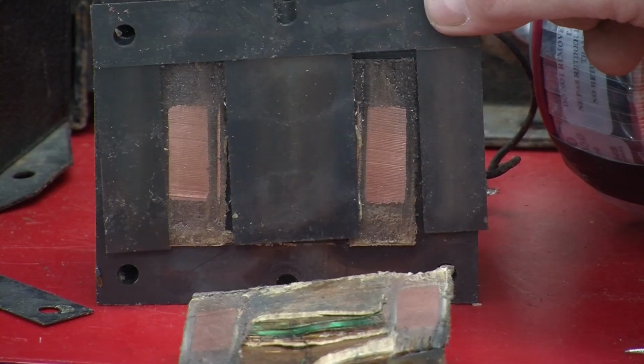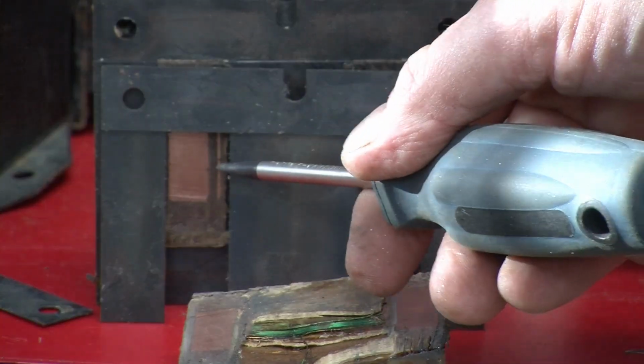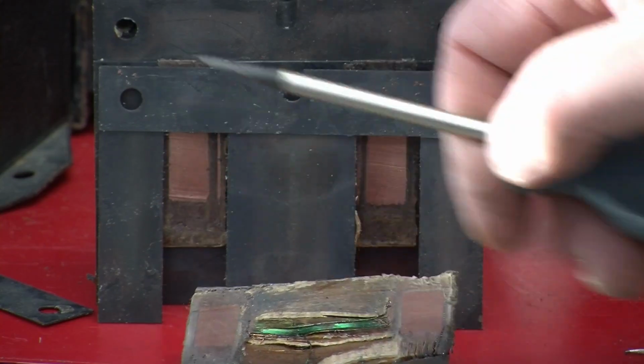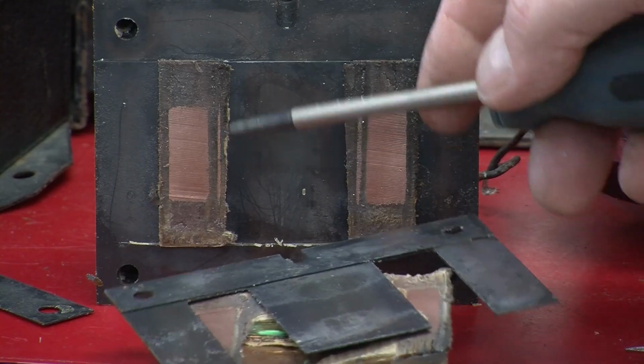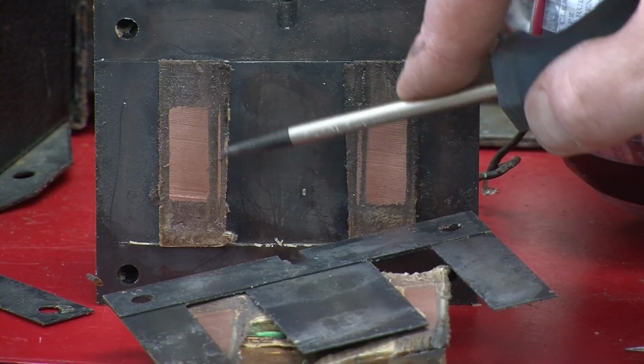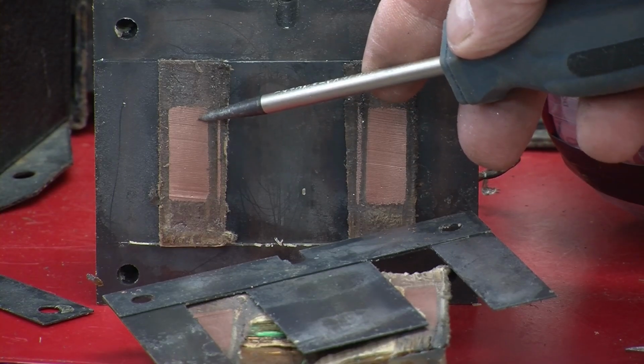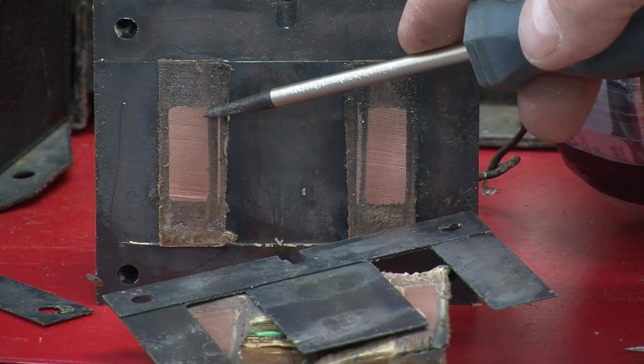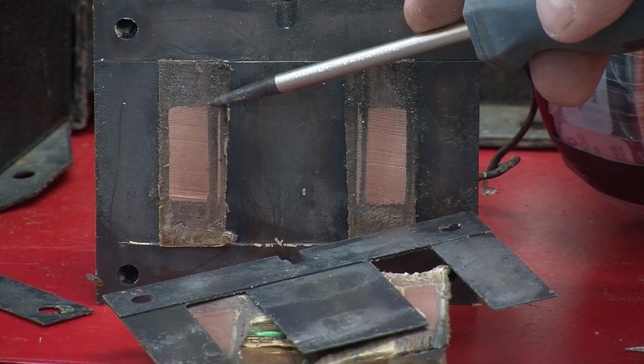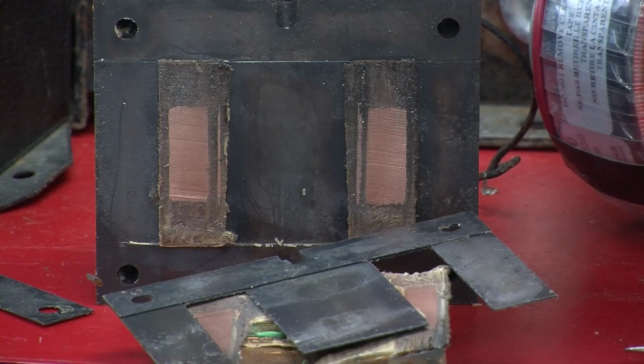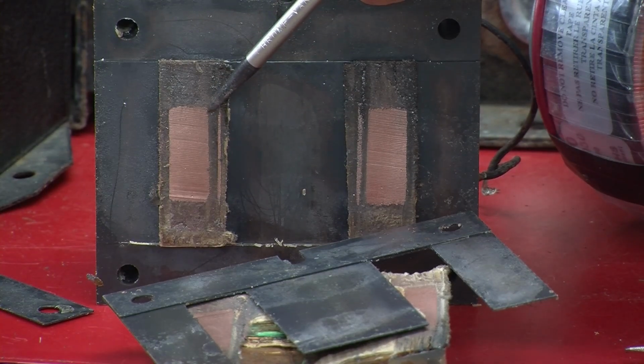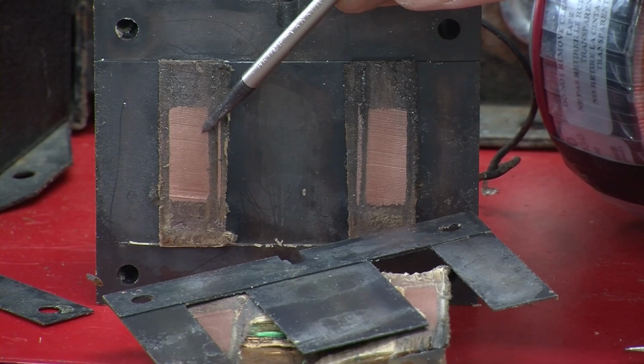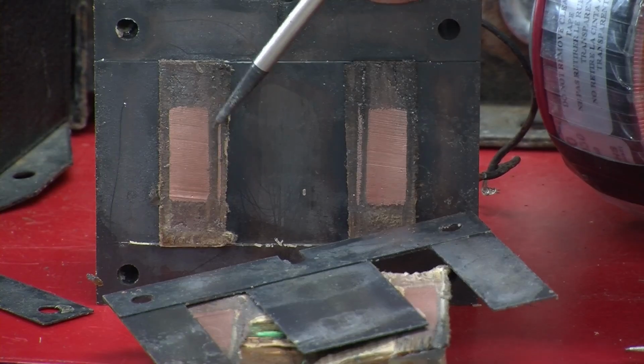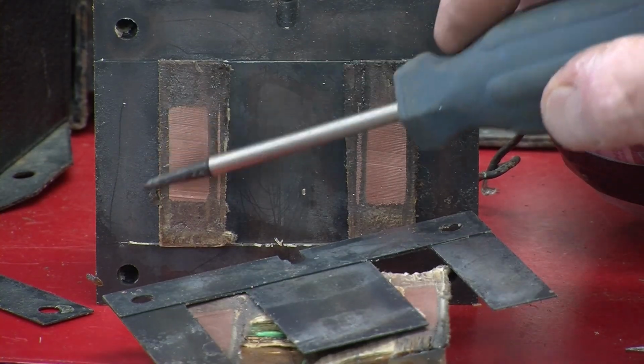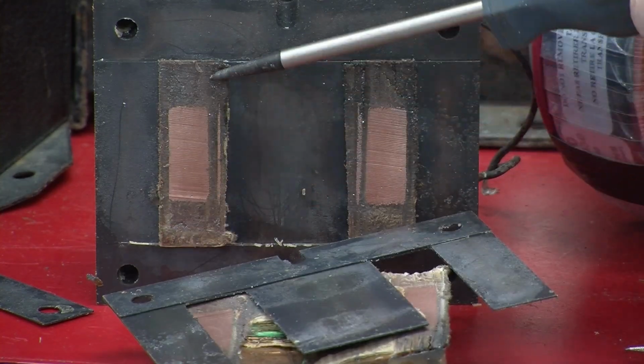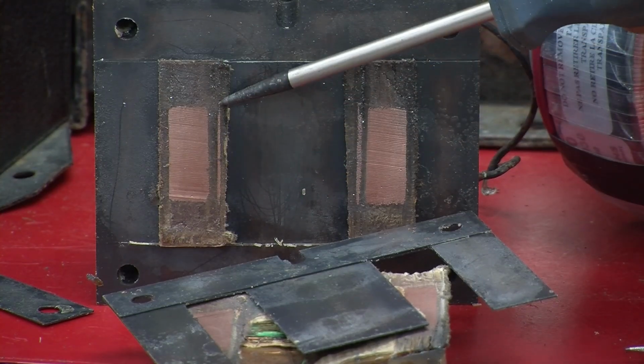And if we make that wire too fine, that limits the amount of current that can go through the wire. And it also means when current flows through the wire, it now has a greater resistance if it's very fine, and there is an amount of resistive loss from current flowing through the wire. And that is called the copper losses. So if you want to have a higher power transformer, you need more space for the windings because you need bigger diameter wires. What that means is you need to make the core bigger so that the hole in the core is big enough to accommodate the windings.